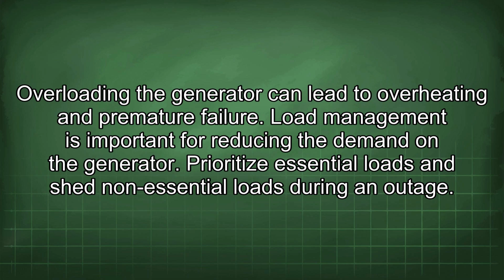Overloading the generator can lead to overheating and premature failure. Load management is important for reducing the demand on the generator. Prioritize essential loads and shed non-essential loads during an outage.